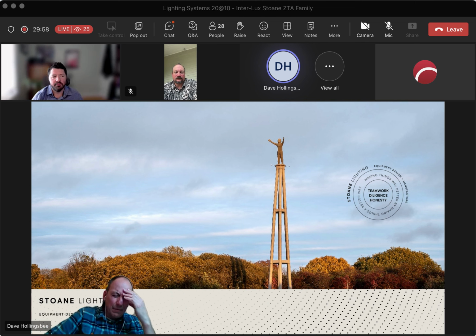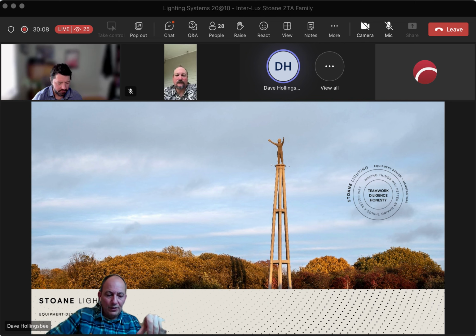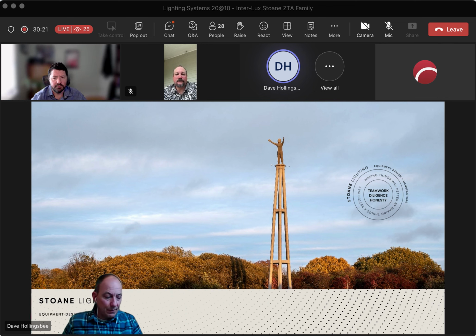Sorry, I listed Casambi, but the other Bluetooth protocols really were only limited by the hardware. And these days, it's becoming more and more common to flash a fairly generic board with whichever protocol you want. I think Bluetooth Mesh is becoming popular. That sort of thing. Silvair have another. Unfortunately, they've not harmonized these Bluetooth protocols. But yeah, the most common one for us would be Zencontrol, which is really capable.